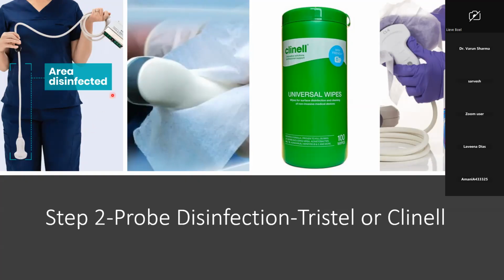So in an ideal world, when I start using my machine, we will take a Clinell wipe, wipe the screen, wipe the surface, wipe the body, including the buttons, and really disinfect the probe pretty much to the portion where I feel that is going to go into the incubator. So you use Clinell that's allocated for the machine. Do not pick up a Clinell wipe that's being used for a baby who's on contact precautions and then start using it on the machine. We have dedicated Clinell wipes which we keep on our machine.